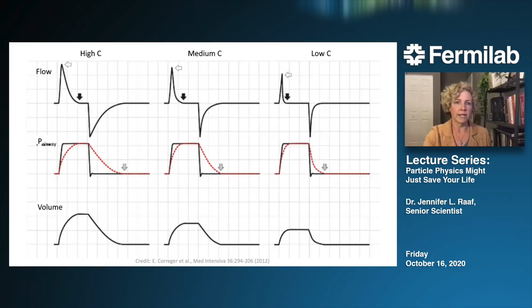As compliance decreases, that overall peak flow also decreases, which you can see in the top row. And the pressure of the alveoli, the red line in the second row, more quickly reaches the same value as the supplied target airway pressure, comparing the red and black lines in the second row. And then on the bottom row, you can see that the volume of air also decreases with decreased compliance. So let me flip back for a second to the resistance, compliance, and you can see there's a large variety in how those waveforms look.